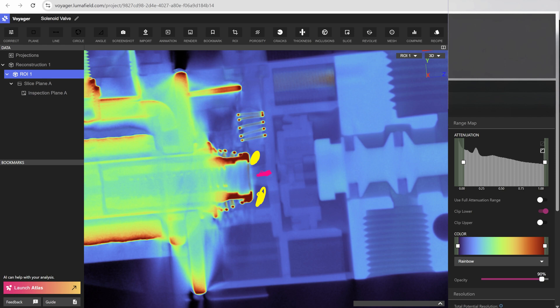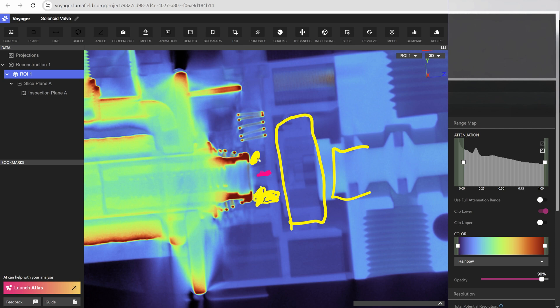When we turn on the solenoid, that's how we get the spool valve to move and change the position. But how do we cause there to stop being pressure? We sweep this, we suddenly lose a lot of radius here, and that's because these are deliberate ports run down the length of the moving element of the solenoid. That's so that pressurized air from this gallery up front can actually reach down the length of this.